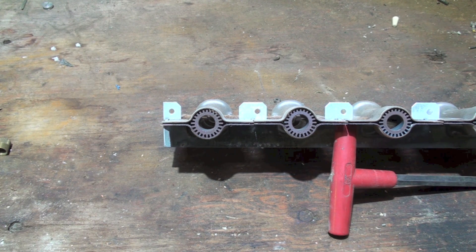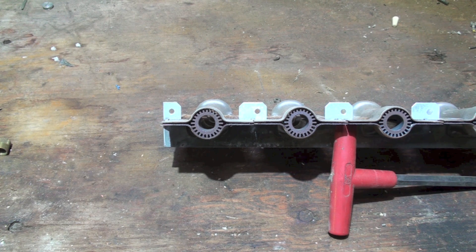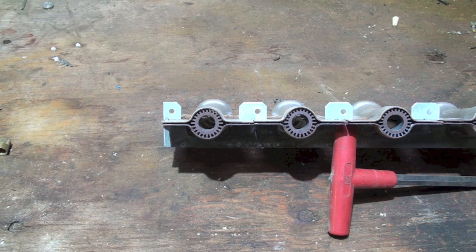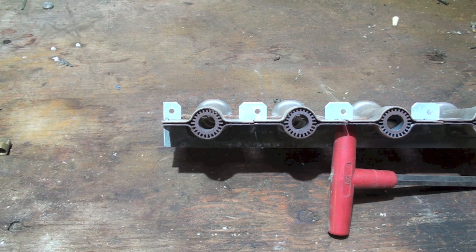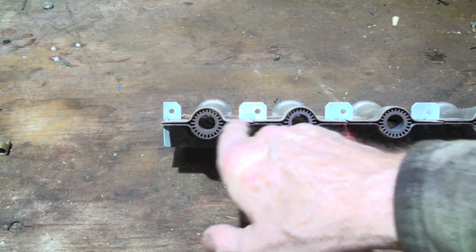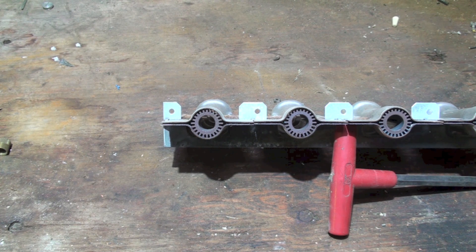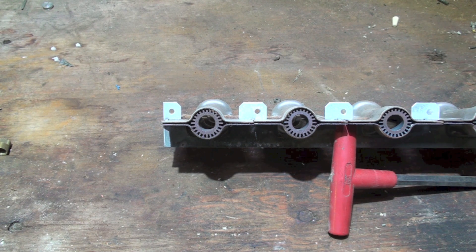So what you end up with is it goes out on flame safety all the time, but if you watch it, not all the burners are lighting. All it takes is a good cleaning, a little bit of a wire brush in there, and maybe a vacuum cleaner, and it will clean up good.